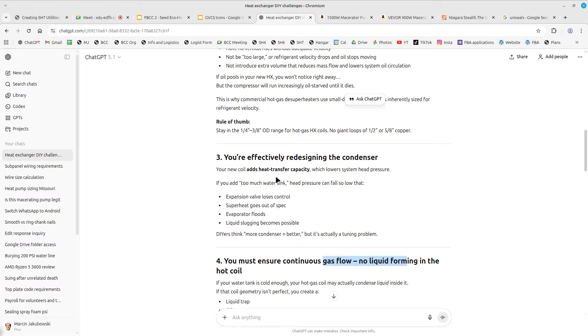Yeah. So let's look at this. We're farmer scientists here. We've got to do all these steps. Another thing, charging isn't a top off. It's a full recap. Yes, you have to know what you're doing. You've got to take measurements, and you've got to have a little refrigerant scale to measure how much you're actually putting back into the system. Water heat exchange: if the water temperature gets too low, you create condensation too early. If the coil is too hot, you're not getting much energy. So we've got to pay attention to details like what the temperatures are. It's not just cut and braze. You've got to kind of know what you're doing, but we're going to do it anyway because we're learning.